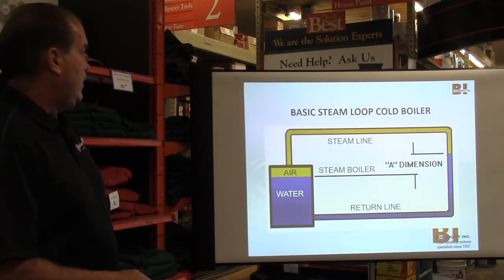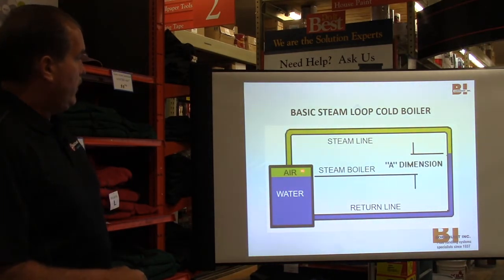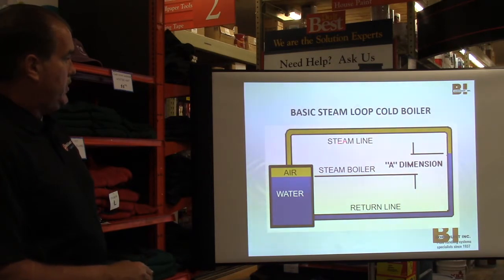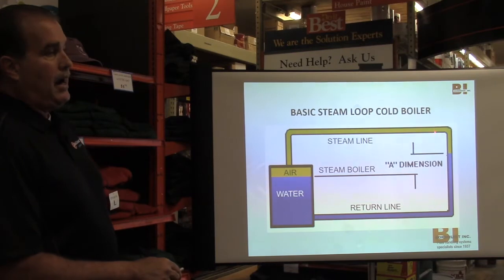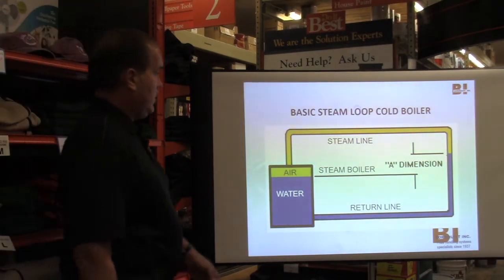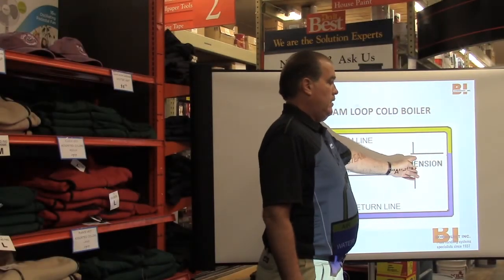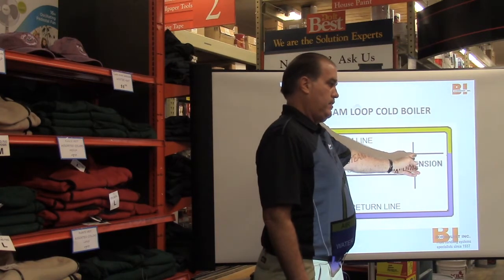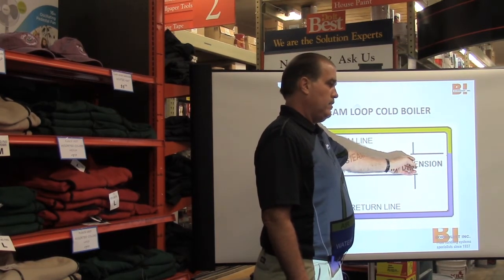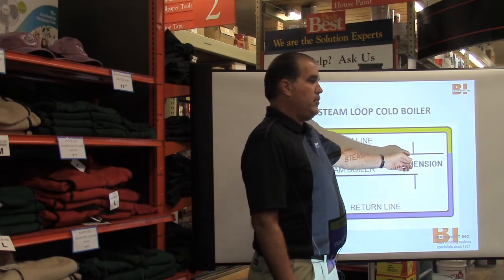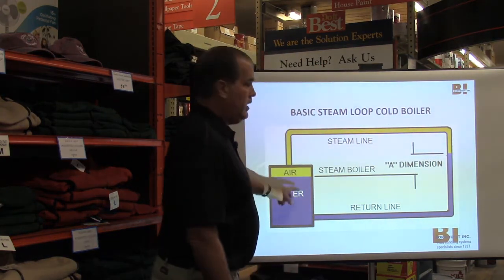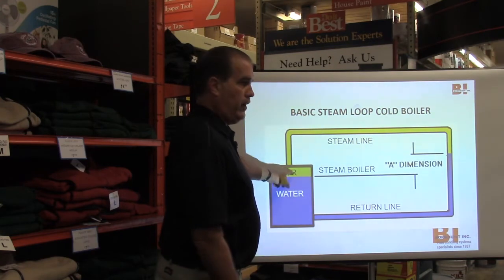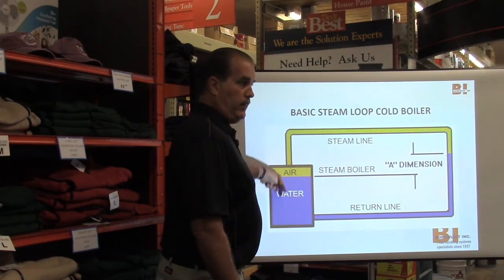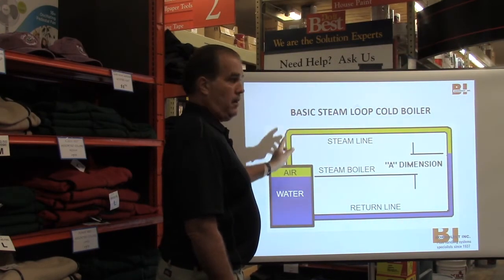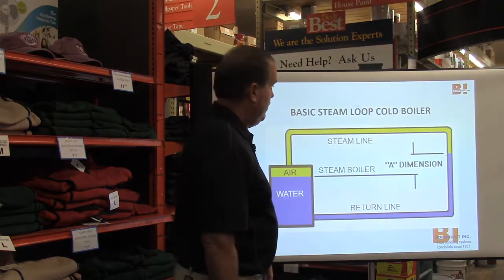And this is what I'm talking about when I talk about a steam boiler. First thing that happens when there's just air in the system, as this boiler starts steaming, it allows steam to come out. Okay? There's a dimension A that the boiler manufacturer will reference in his literature. It's about 18 inches. And the reason you need that is as you heat up this water and it turns to steam, there's pressure here. So there's pressure pushing down on the water line, but there's pressure pushing up, and that's what pushes the steam out into the system.